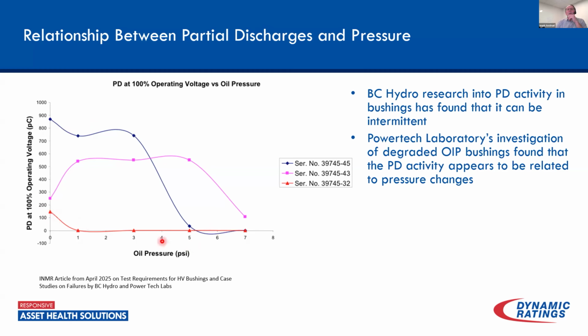So obviously there must be some other factors here, because here we've got one where it increases and then later decreases. But in general, the overall result of their analysis was that there's typically a direct correlation between partial discharge and pressure. So as we go through that thermal cycling on those units, it's going to have an impact on the partial discharge. When pressure's up, we're not going to see it. But when it comes offline, especially if you have rapid cooling, if we're cooling down very quickly, we can expect to see increased partial discharges on those units.